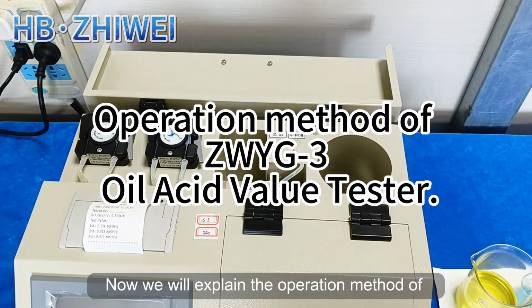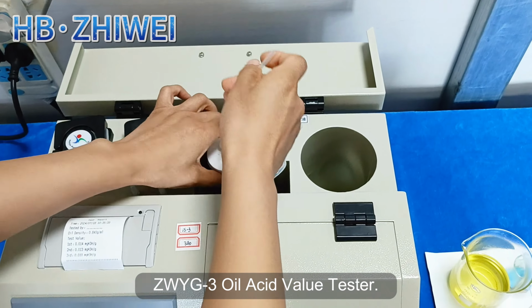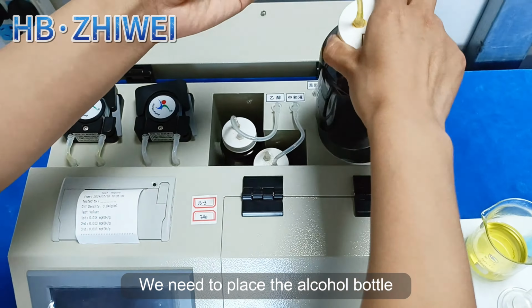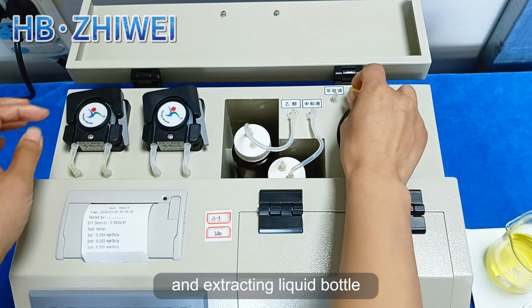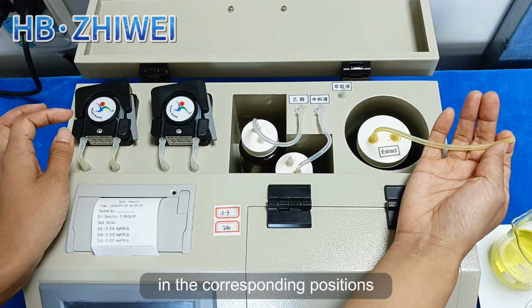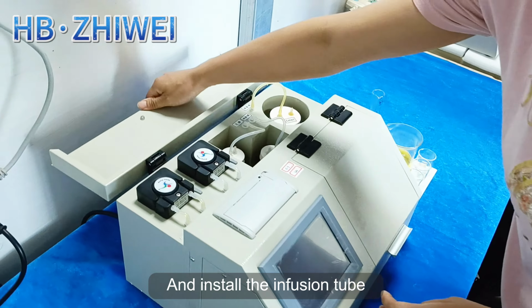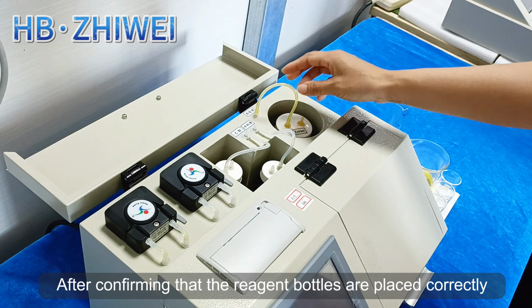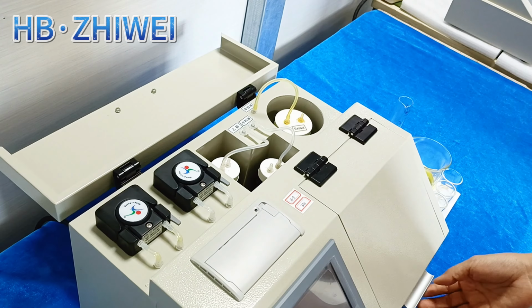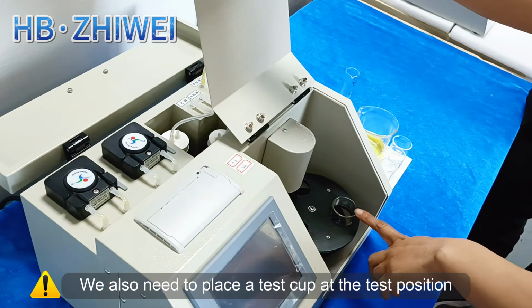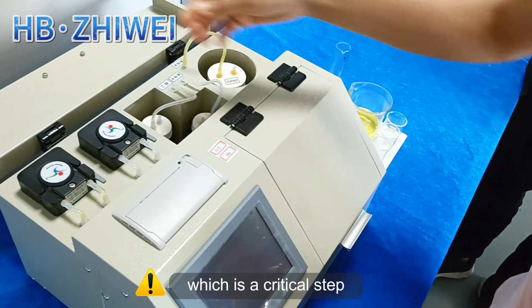Now we will explain the operation method of the ZWYG-3 oil acid value tester. We need to place the alcohol bottle, neutralizing liquid bottle, and extracting liquid bottle in the corresponding positions and install the infusion tube. After confirming that the reagent bottles are placed correctly, we also need to place a test cup at the test position, which is a critical step.